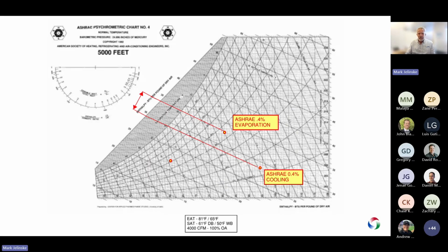So let's say that we've got a problem at hand. One of our sales engineers has a client who needs specific conditions being delivered. We're being asked to provide 4,000 CFM at 61 degrees dry bulb, 50 wet bulb. And we're told it's 100% outside air. So what value should we use for that outside air?